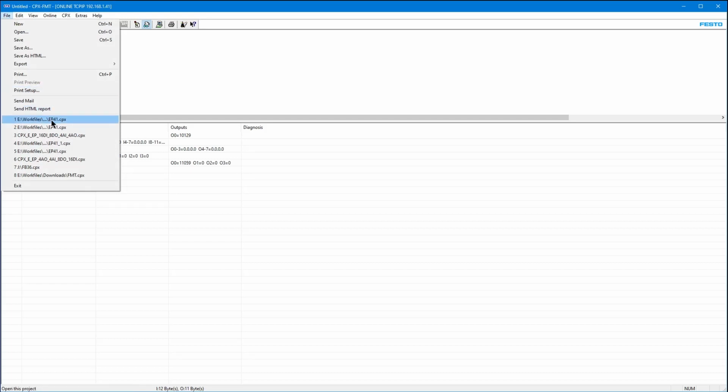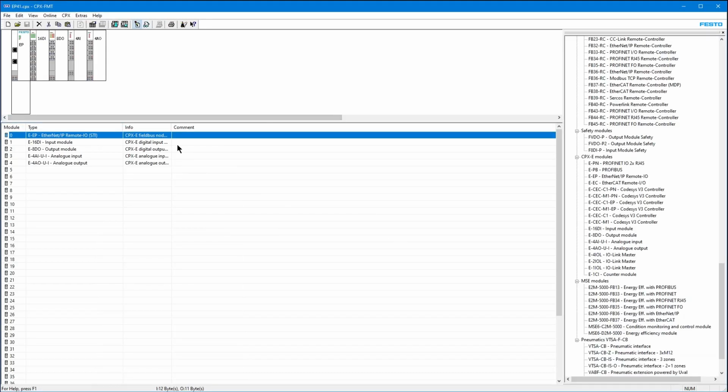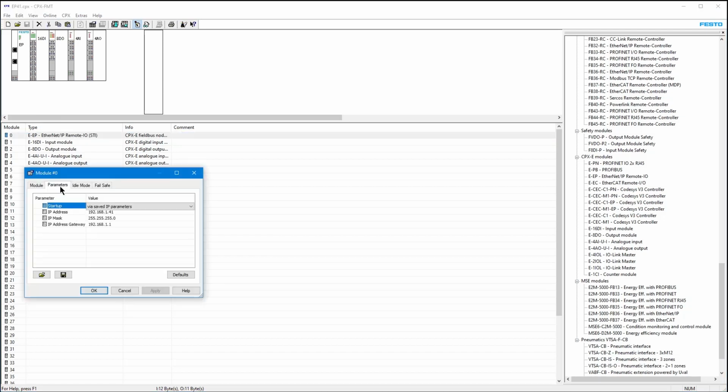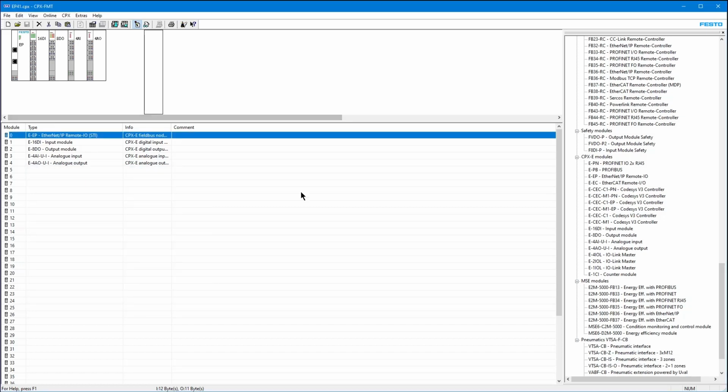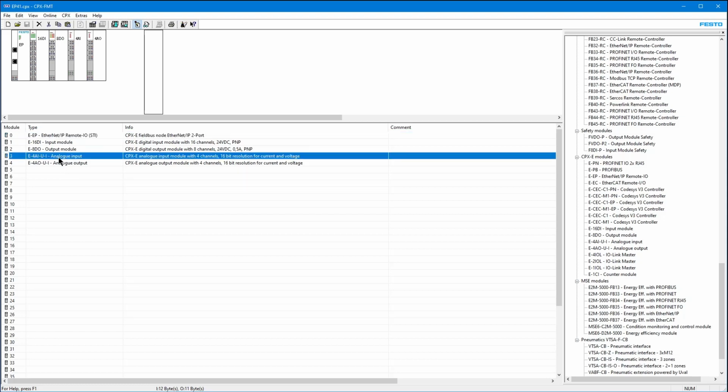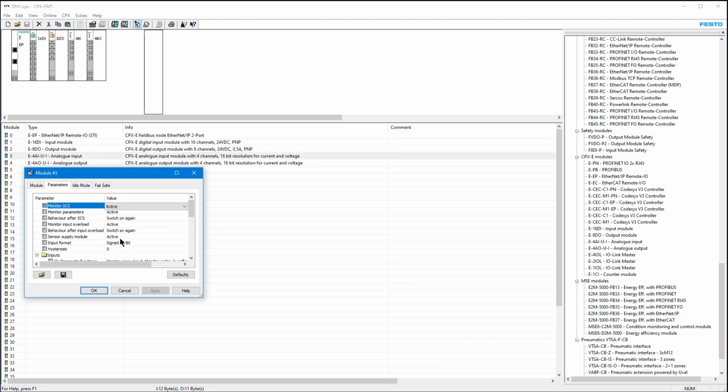So I'm going to go to this right here, and I've already saved this, so I've just called it EP41 because in this case it's an IP address of 41. Okay, the first objective of this Festo Maintenance Tool software is to configure the parameters of the various devices. So in my case, for example, I have an analog input module, and I've already gone through. I've said that this particular device is 0 to 10 volts.